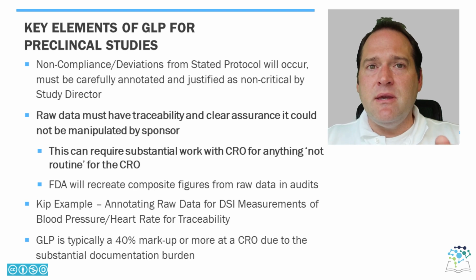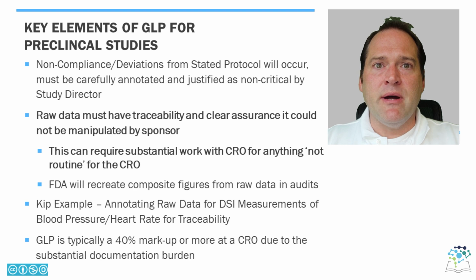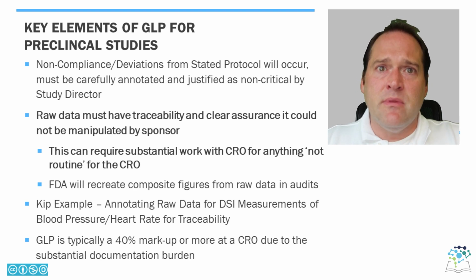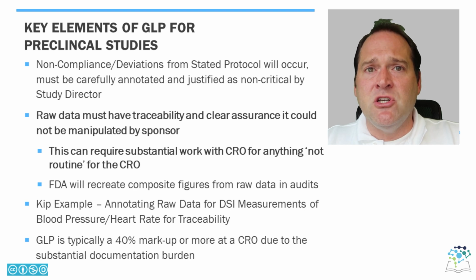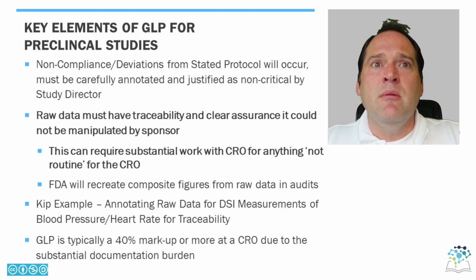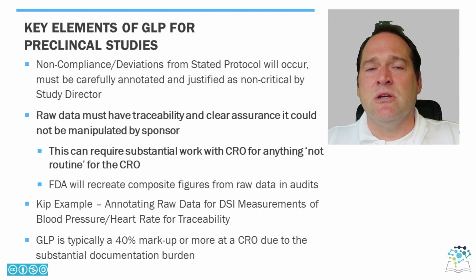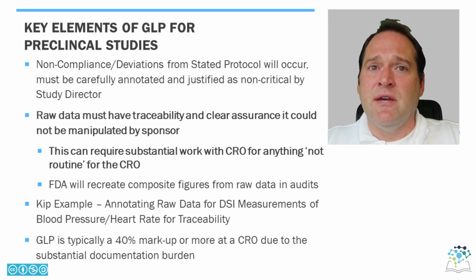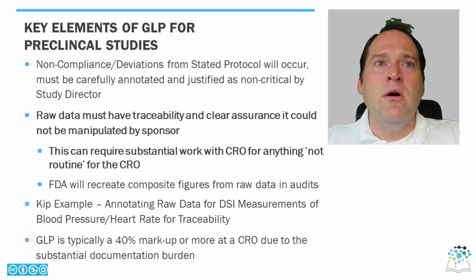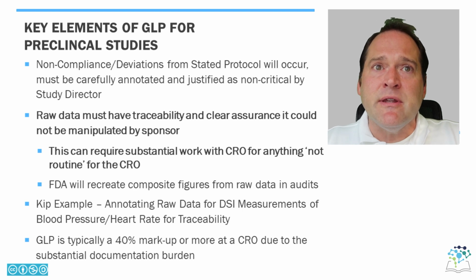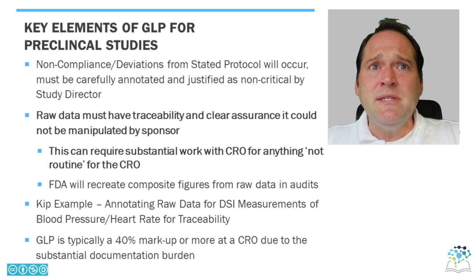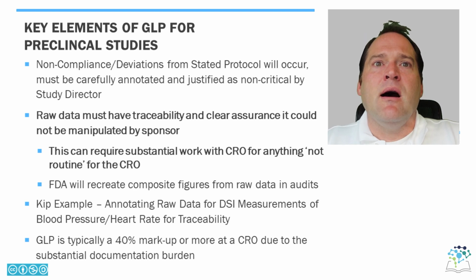So in GLP, you outline a protocol, but it's important to note that there are sometimes non-compliances and deviations from that protocol, even in a GLP study that's successfully used. But they must be carefully annotated and justified as non-critical to the safety outcomes by the study director, who's typically independent. As I mentioned before, raw data must have traceability and clear assurance it could not be manipulated by the sponsor. Now, this can actually require substantial work with the CRO for anything not routine to them.